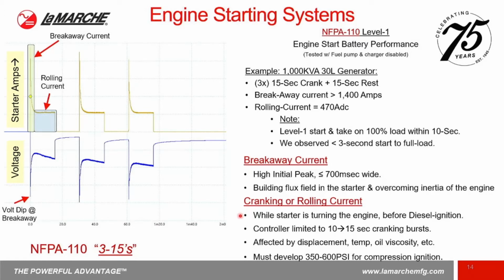This is while the starter is actually turning the engine, but before you've actually accomplished diesel ignition. The controller inside the generator will normally limit this time to somewhere in the vicinity of 10 seconds or maybe 15 seconds. The reason we go for 15 seconds is because NFPA 110 requires that as how much energy you should have in a level 1 system. Some factors that affect this are the engine displacement, the temperature, and the oil viscosity. All these factors affect what this rolling or cranking current will actually be.